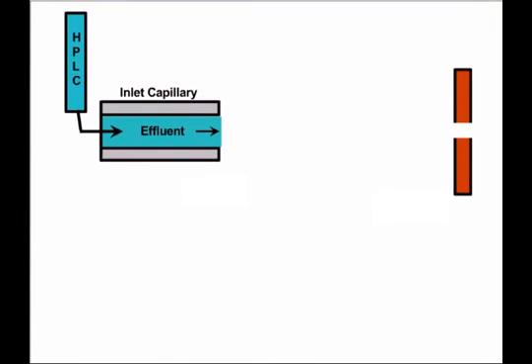If we look at an electrospray interface, it's a very simple device. We have an HPLC column which feeds the effluent from that column through an inlet capillary. That capillary is in the atmospheric pressure region of the interface. This atmospheric pressure region is a closed region, but it's not evacuated — it isn't under vacuum. Atmospheric gases are simply present.